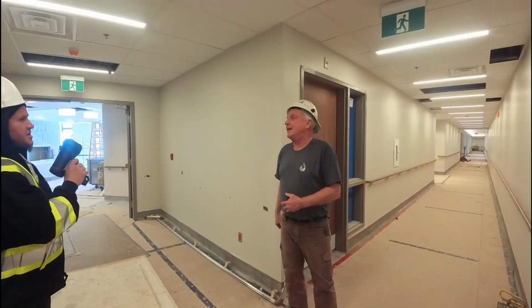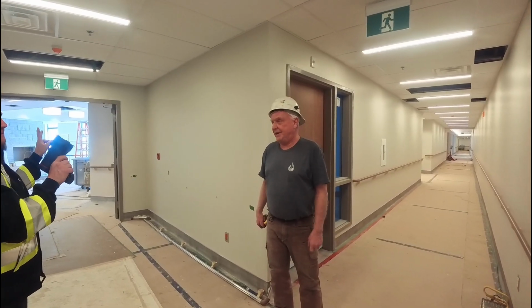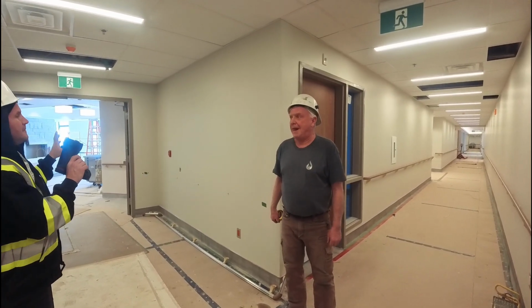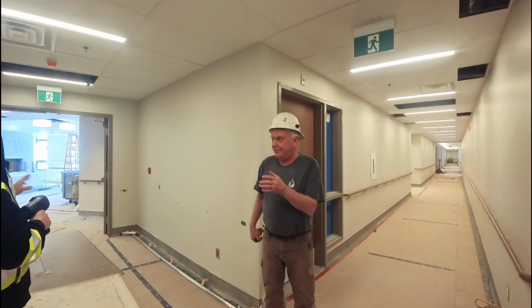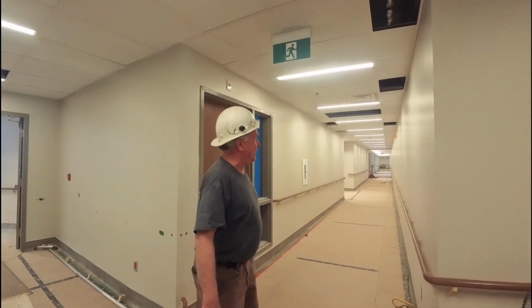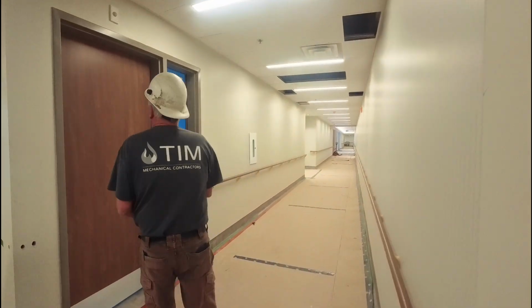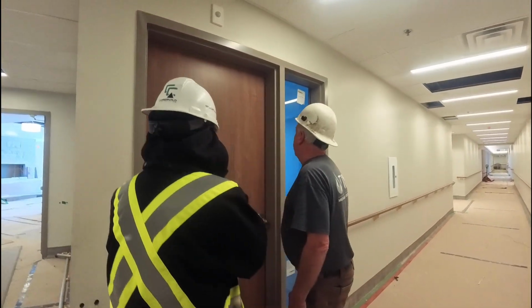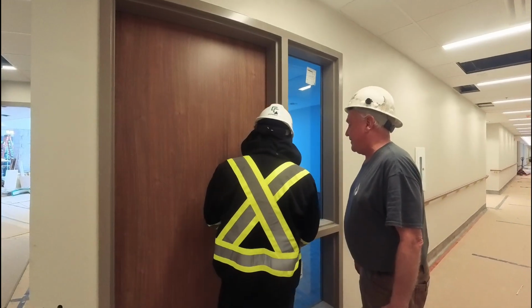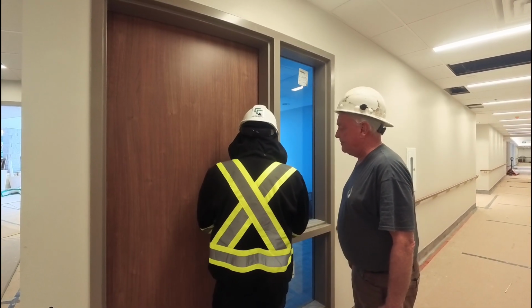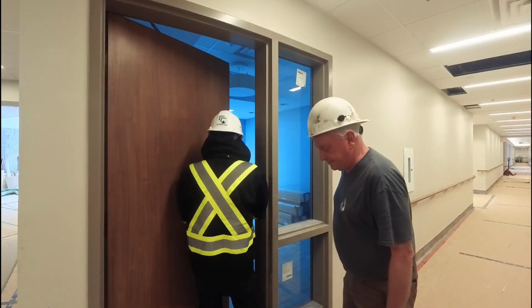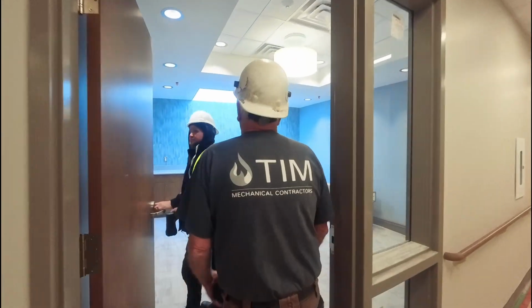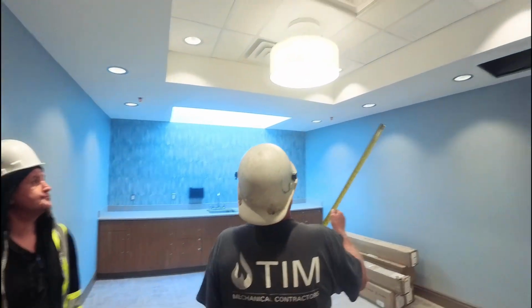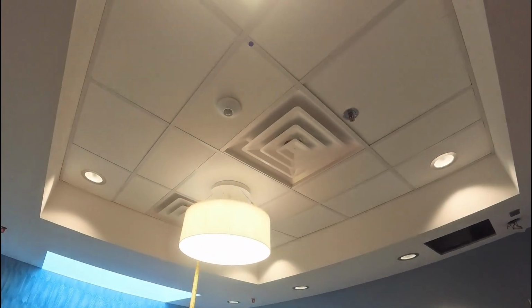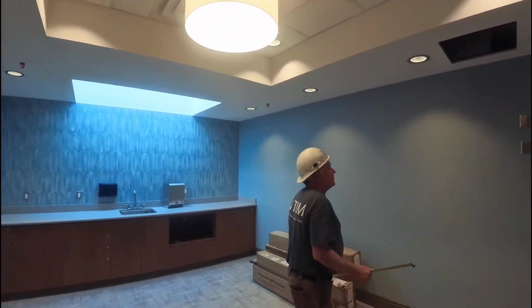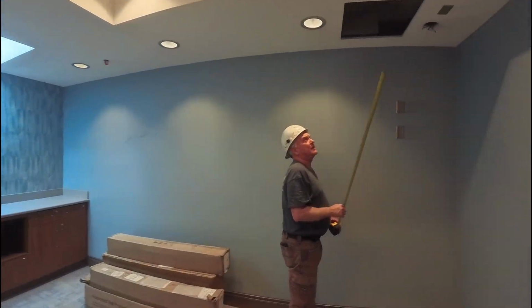So where were the filters contained, people? There's no filters in that, it's a VAV. A VAV doesn't have just the damper that's moving. It's a damper that controls the volume. And they also have some kind of heaters in them for temperature, and that VAV is picking up these two diffusers here, the one that's out there in the hall. So now, is there going to be a filter in here to change?